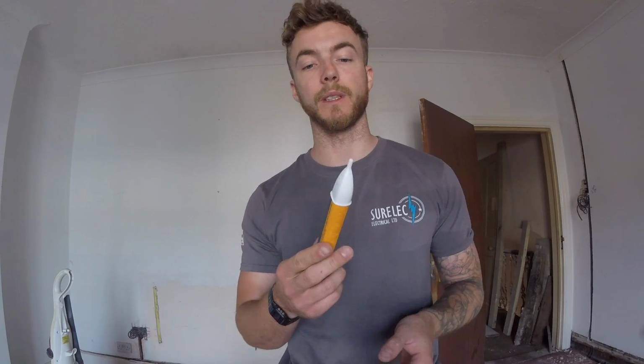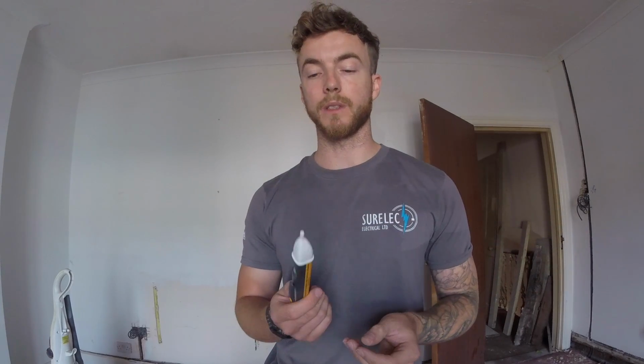So say if you made that whole fuse board dead, this is a good way just to check exactly what cables you're cutting through from which fuse board, because this will let you know if a cable, say a twin and earth cable, is live, for example. So they are quite handy, they are quite quick, but you should always rely on safe isolation before one of these. These are just an added little feature really. But nonetheless, a good little bit of equipment most electricians do use, so yeah, probably worth having.